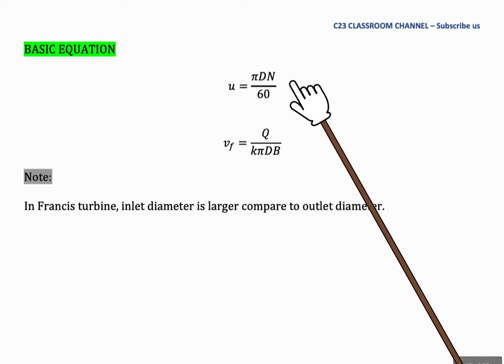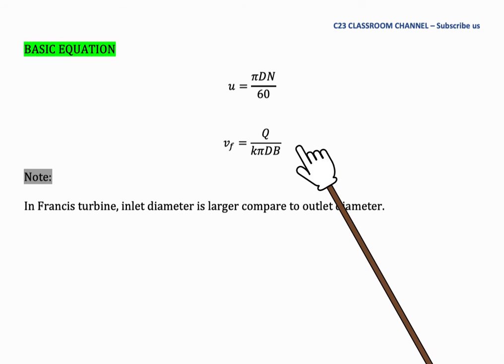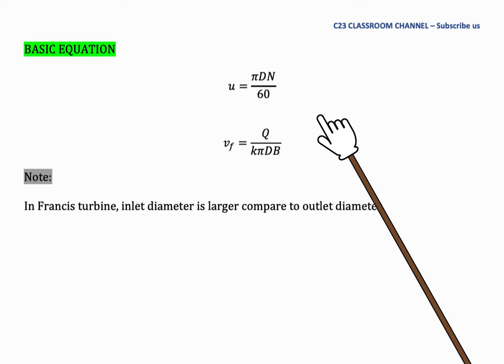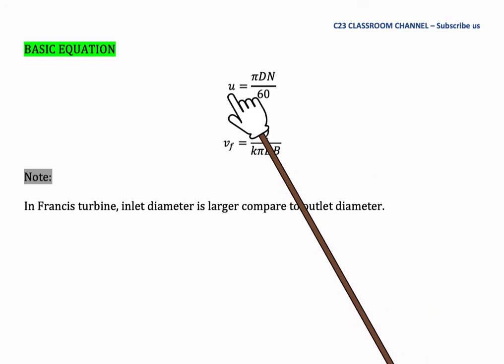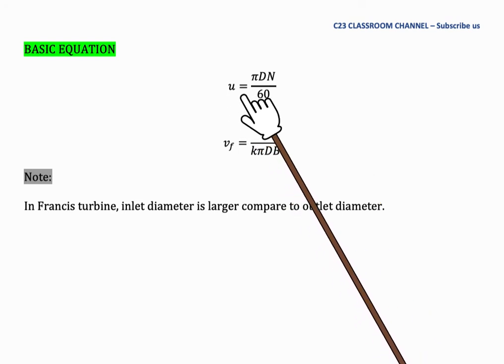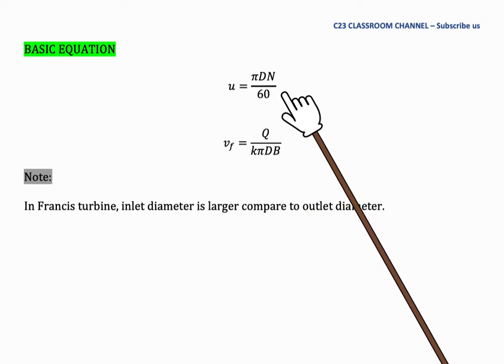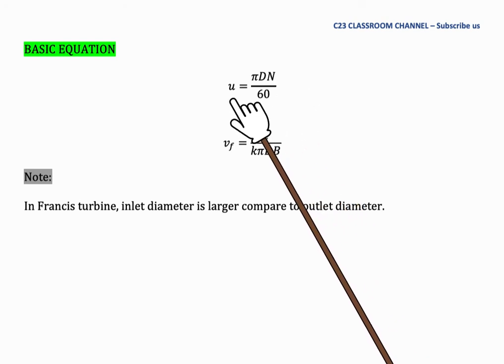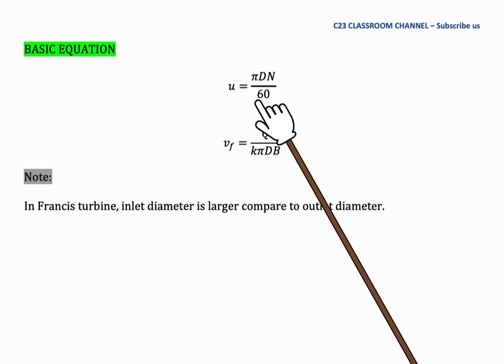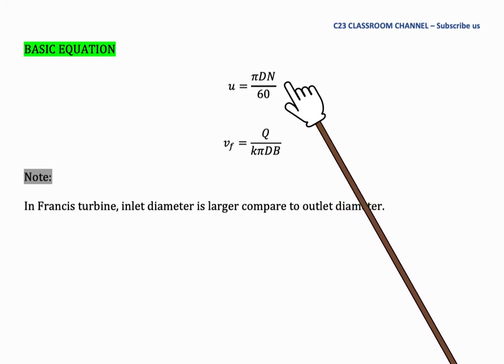And these are two basic equations that we can calculate using equations in Francis turbines. It is the same as the equations we use in centrifugal pumps. Number one is tangential velocity U. It equals π DN over 60. So when you want to calculate U1, you need to use diameter at point 1 to fulfill this equation.